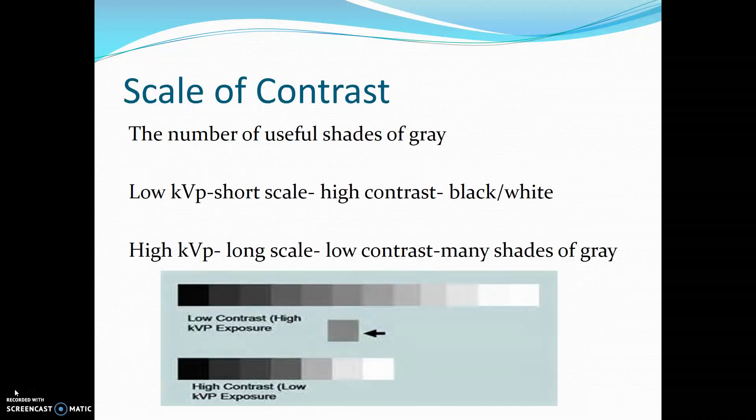The scale of contrast is the number of useful shades of gray. Low KVP creates short scale, high contrast, black and white images. High KVP creates long scale, low contrast images with many shades of gray.